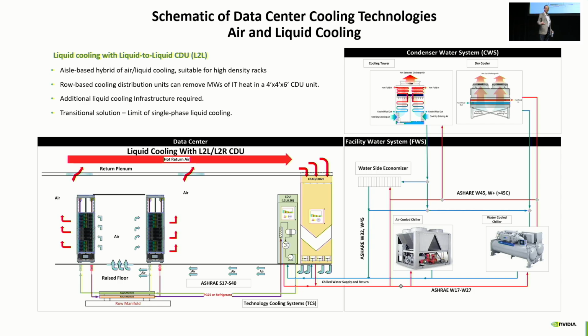Now we have something in our hands. I can have one box that can remove 2, 3, 4 megawatts of heat from my racks. All I need to do is plumbing. Bring liquid in, and make sure that liquid that goes into the racks are reliable, as good as what used to be with the air.